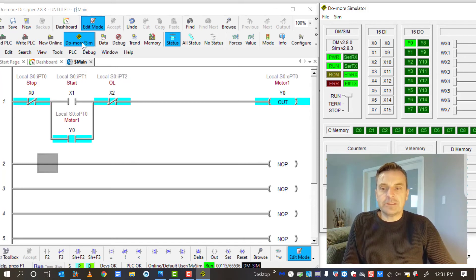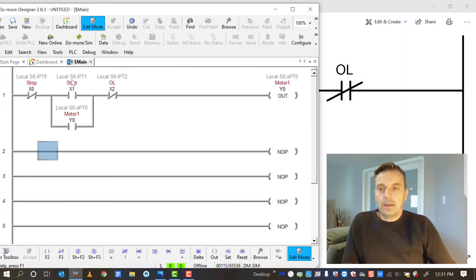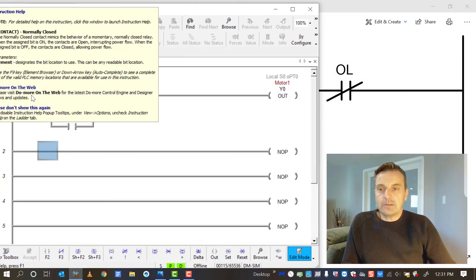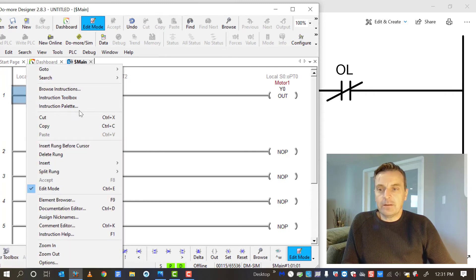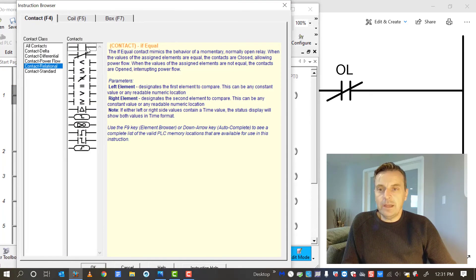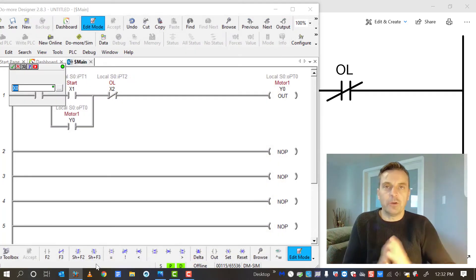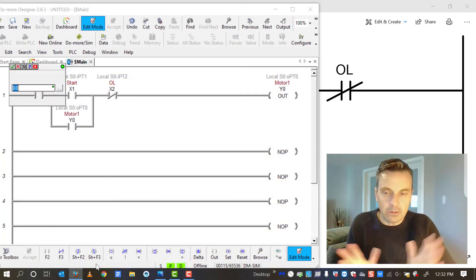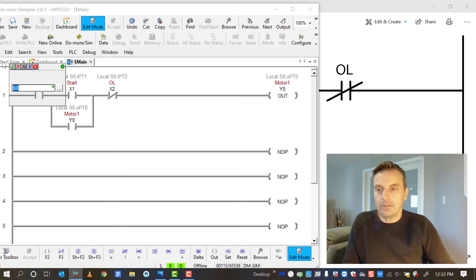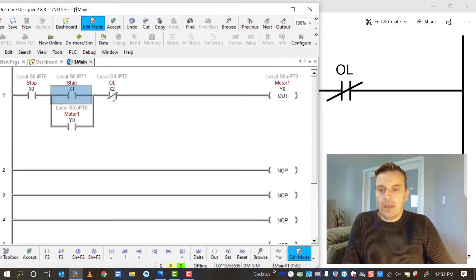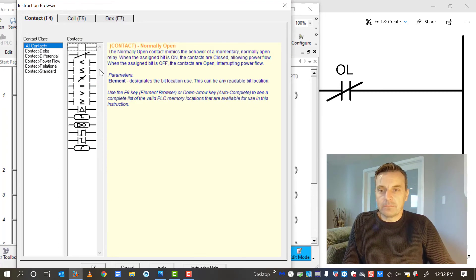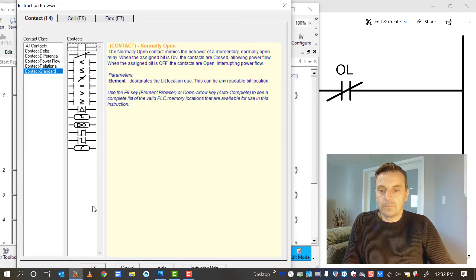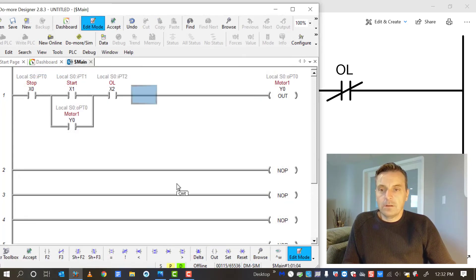Okay, so how do I fix this to jive with what's out in the field? Well, let's turn the simulator off and then let's change these. So I can right click on that and I can change that instruction. I'm going to go to what the program refers to as a normally open contact. I don't like that term, but we'll call it that. And then I'll do the exact same thing for the overload.